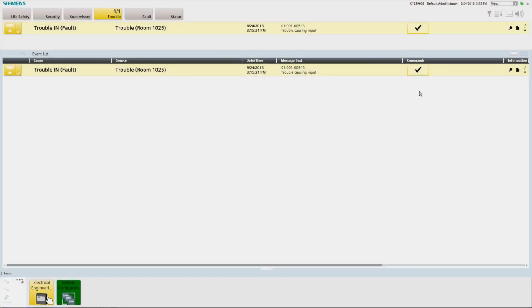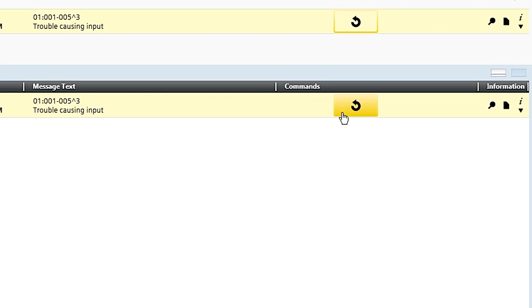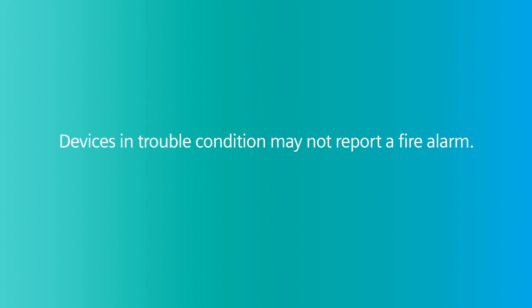A trouble is indicated in the summary bar by the yellow flashing trouble lamp and the yellow flashing fire panel icon in the node map. In addition, a yellow event will be displayed in the event list with a yellow flashing event icon and the workstation audio indicator will sound. To acknowledge the trouble signal, press the acknowledge button located in the commands column in the event list. The workstation audio indicator will be silenced, and the trouble event lamp, event icon in the event list, and the source fire panel icon in the node map will change from flashing to steady. When the trouble condition has been cleared, you may need to reset the panel to restore to normal standby condition by pressing the reset button. Warning: devices in a troubled condition may not report a fire alarm.